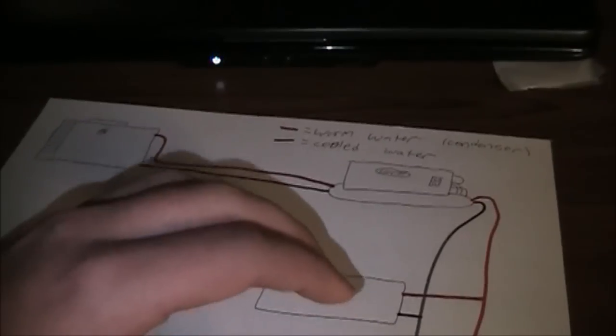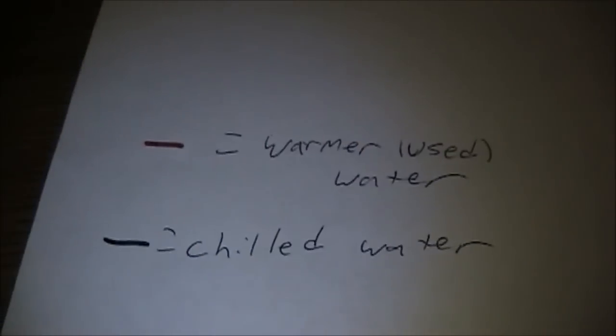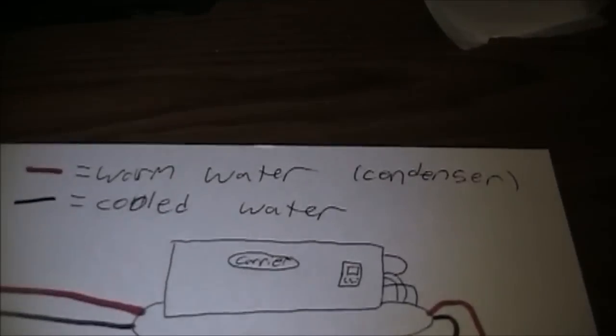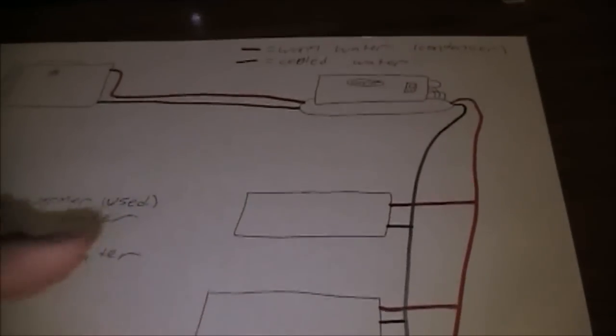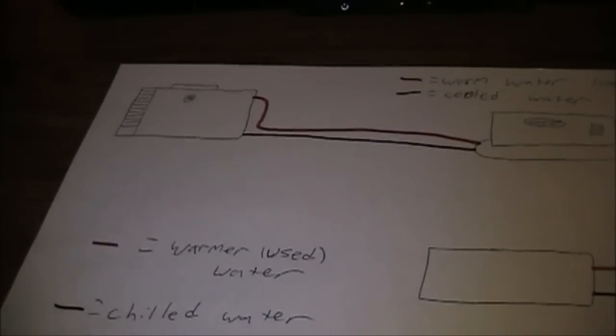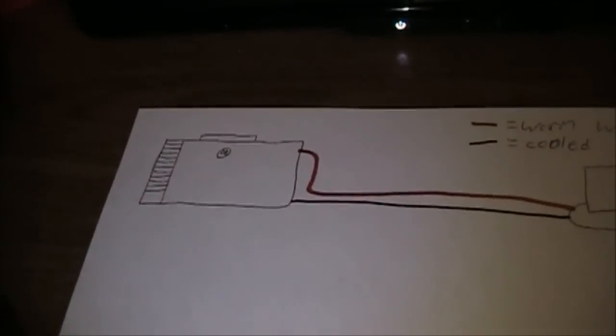And that return temperature is what the air handlers are pulling in. See, this is what this represents, and that's what this represents. There's also pumps to pump this water as well. So that is basically how a chilled water system works—liquid-cooled chiller—and that's how a cooling tower cools water.